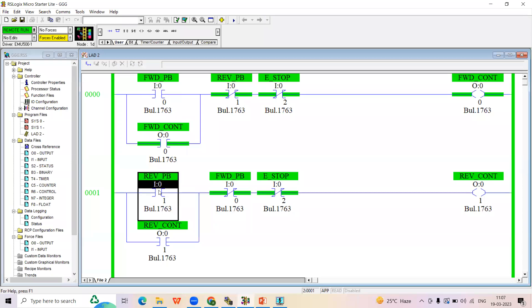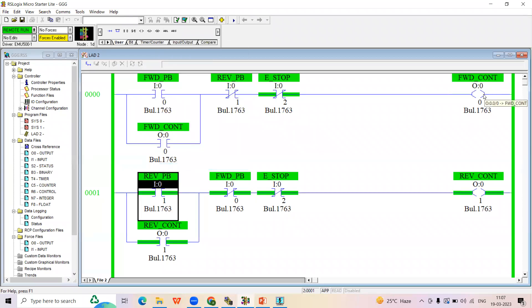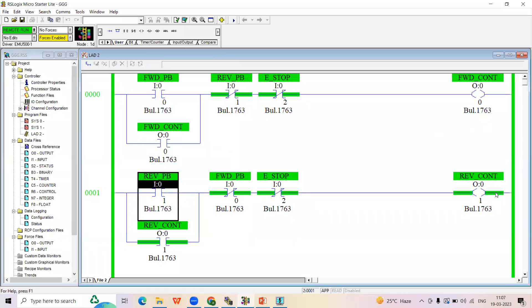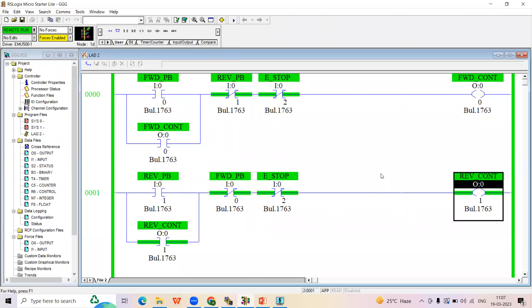Right-click on the forward push button and select 'Toggle Bit' to simulate pressing it. Now it turns green — the motor is running in the forward direction. Release the button by toggling again — the motor continues running due to the holding contact. When the operator presses the reverse button by toggling it, the forward contactor automatically stops and the reverse contactor picks up. This happens because the reverse push button address is used as NC on the forward rung — when I1 is pressed, that NC opens and disconnects the forward contactor while the reverse contactor energizes.